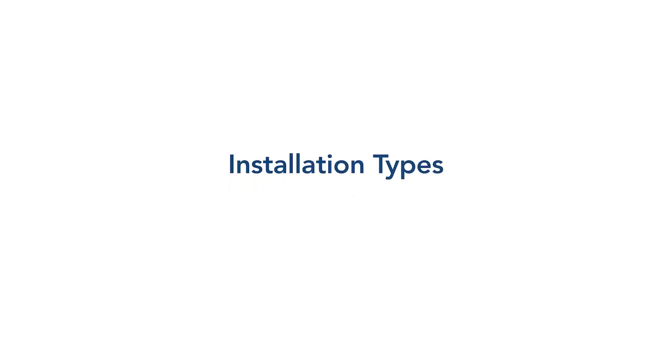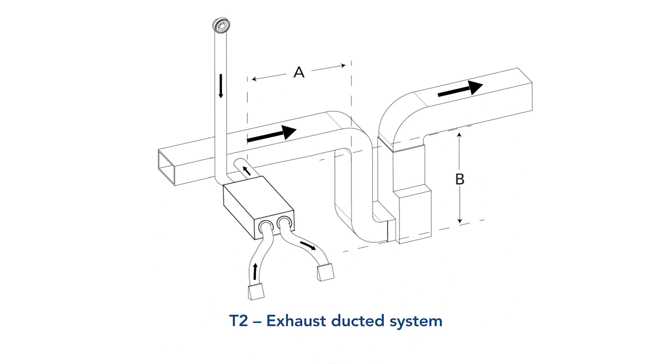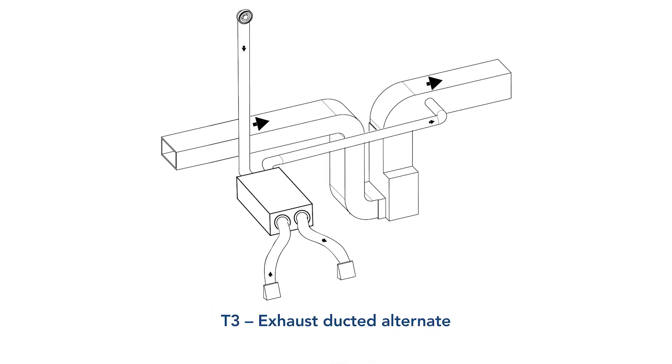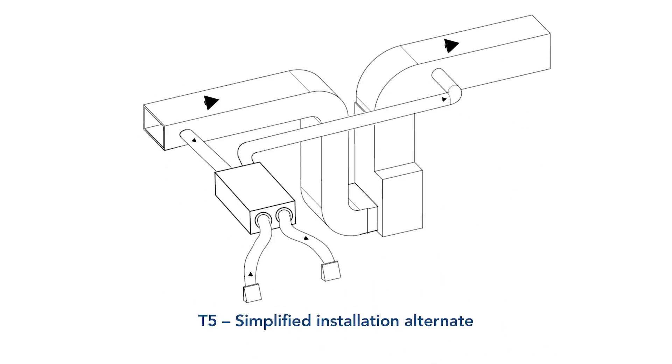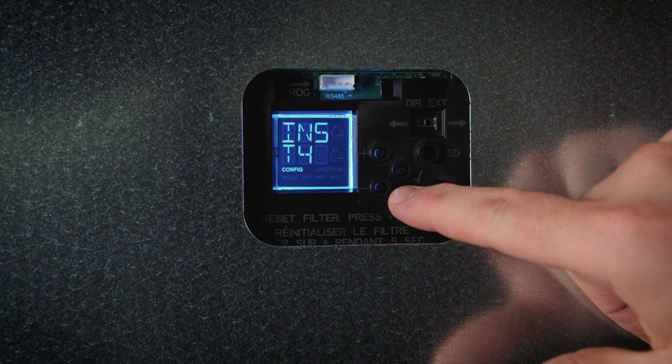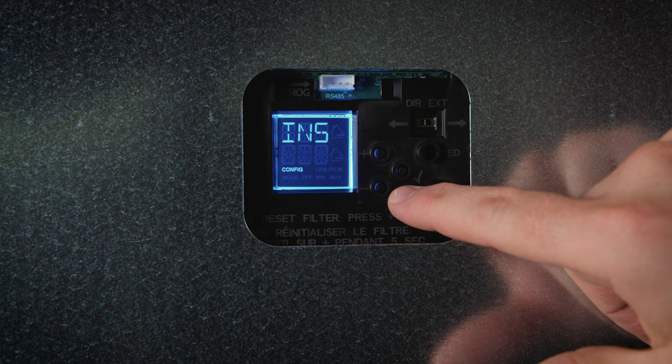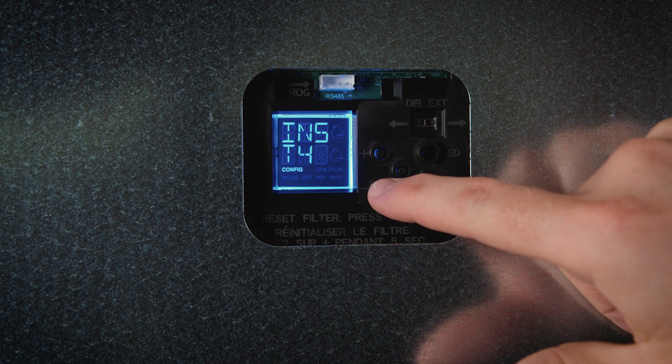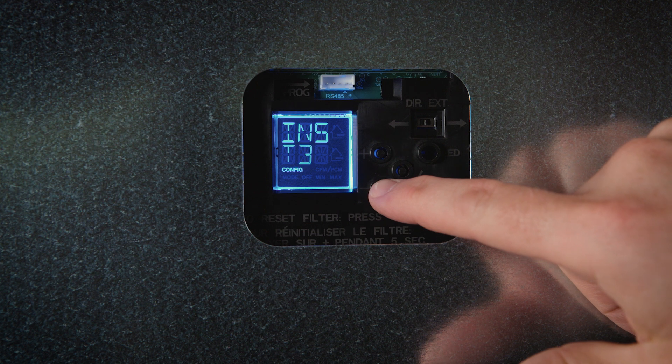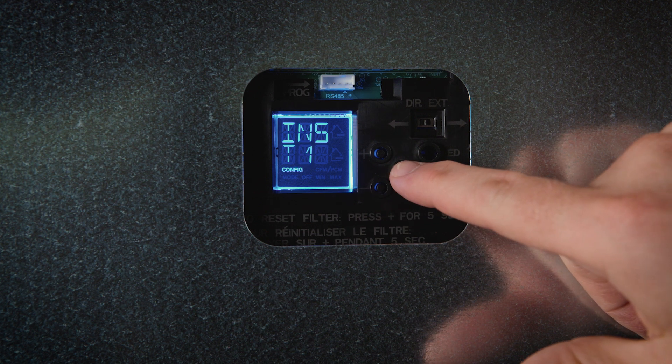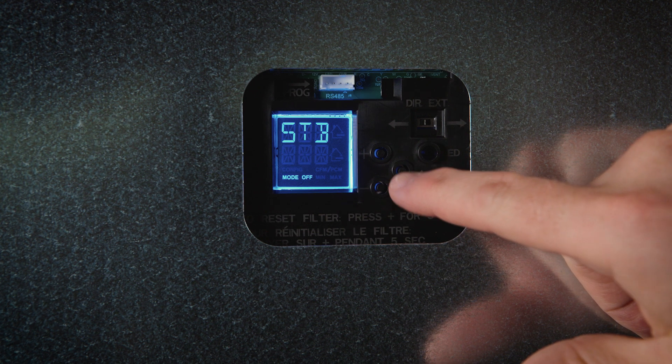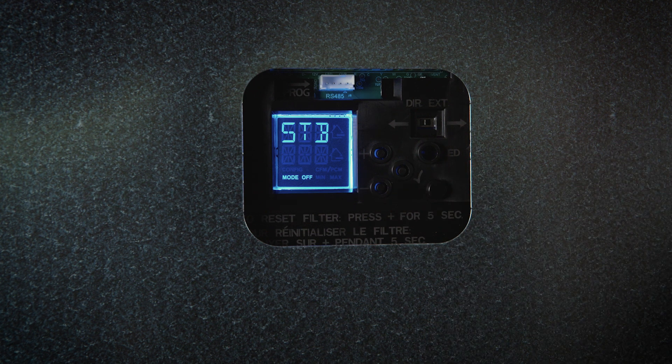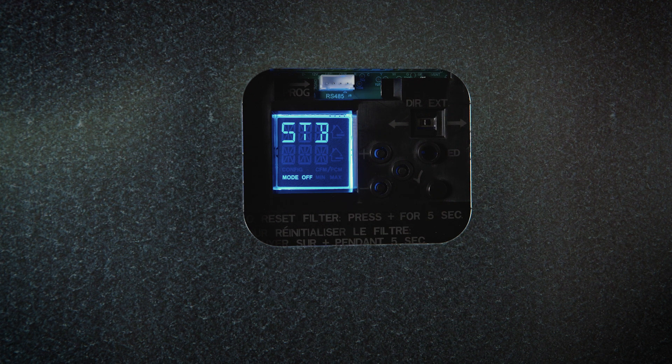Choose from the following installation types: T1, fully ducted system; T2, exhaust ducted system; T3, exhaust ducted alternate; T4, simplified installation; and T5, simplified installation alternate. Choose the installation configuration using the plus or minus buttons and by referring to the installation manual. Select the installation configuration on the LCD screen and press the check mark to confirm.